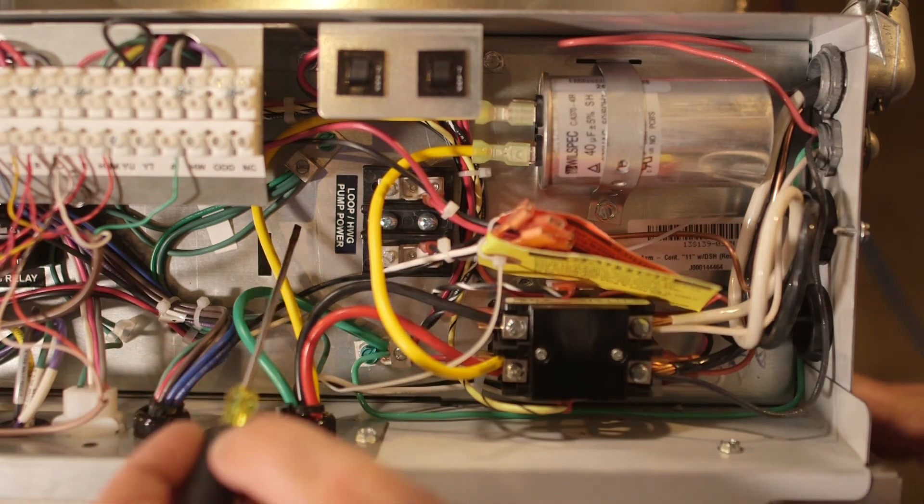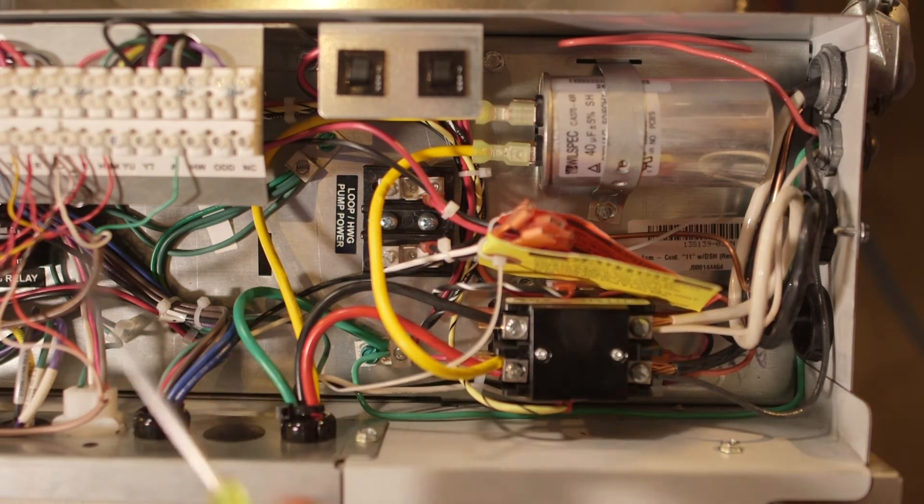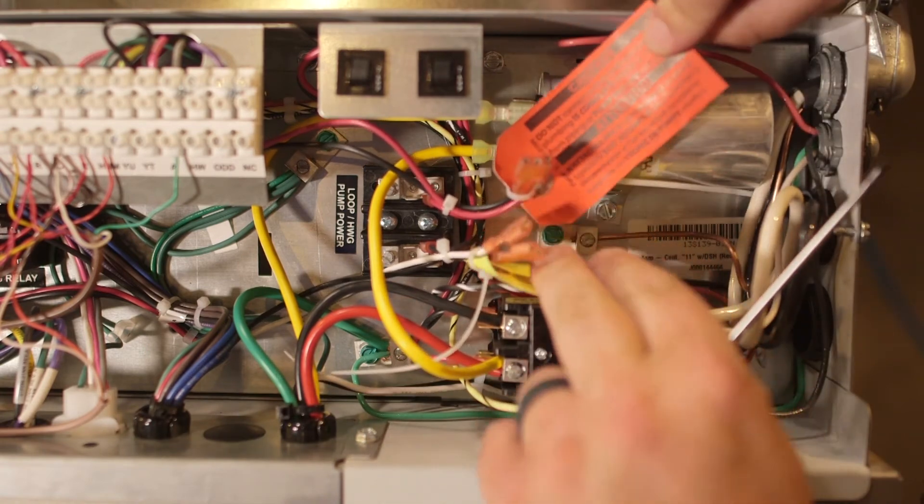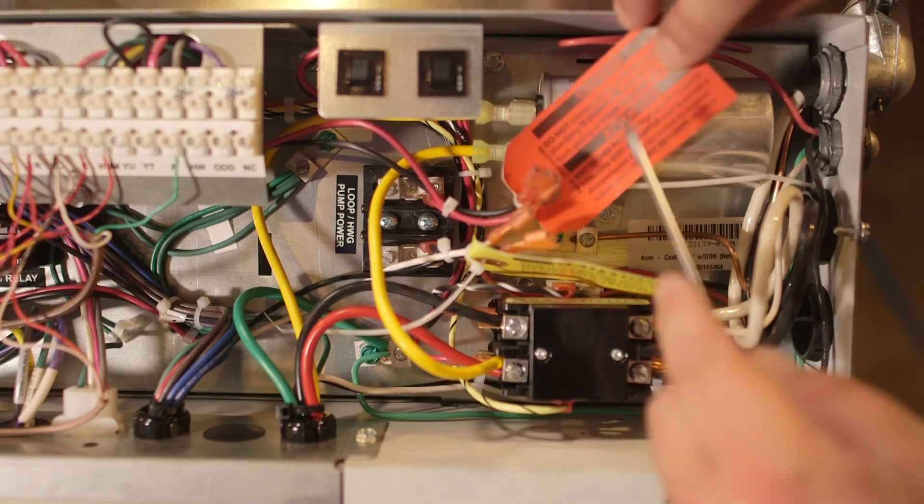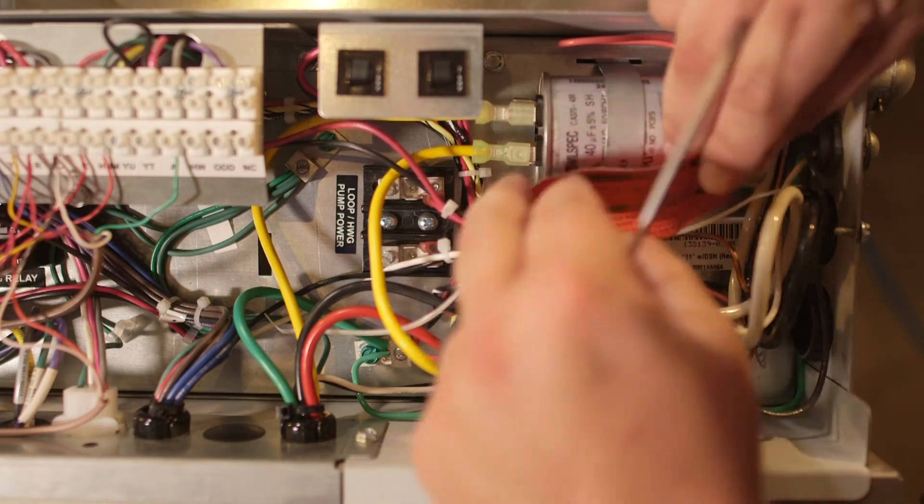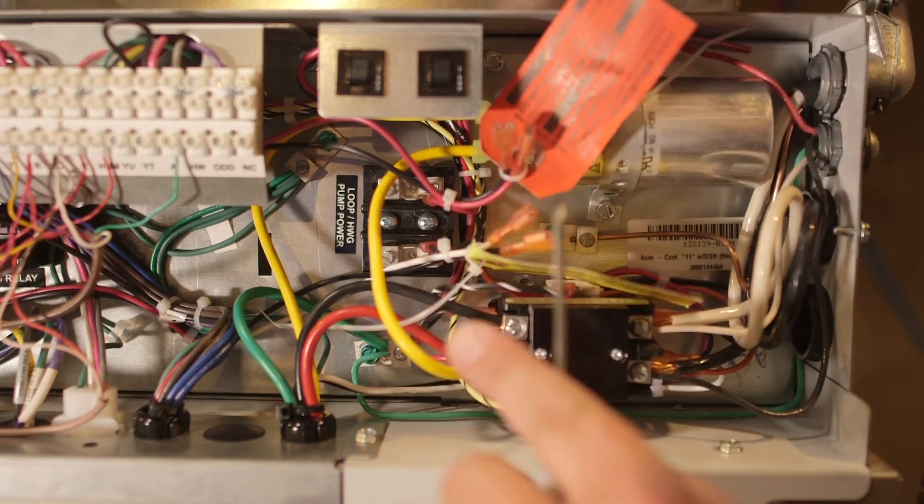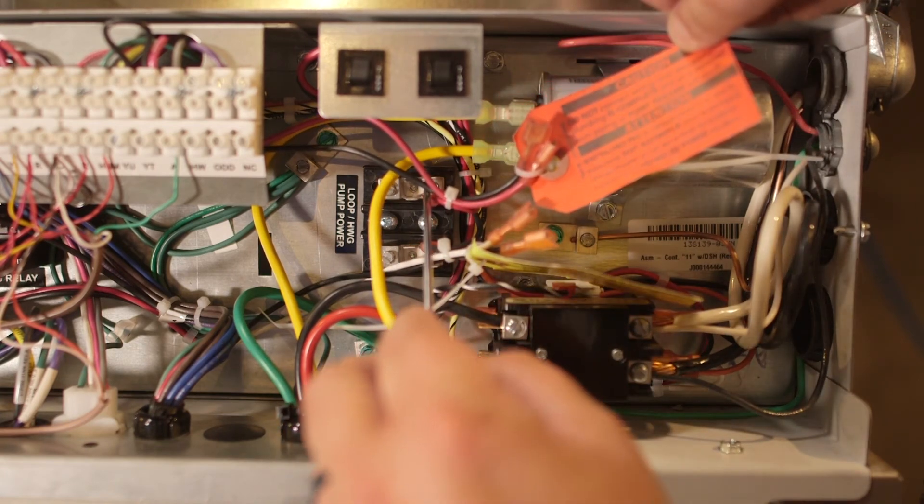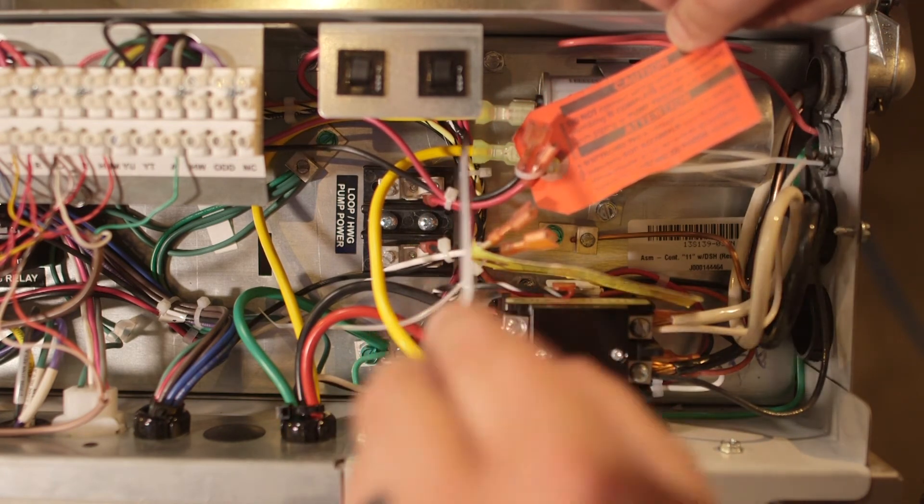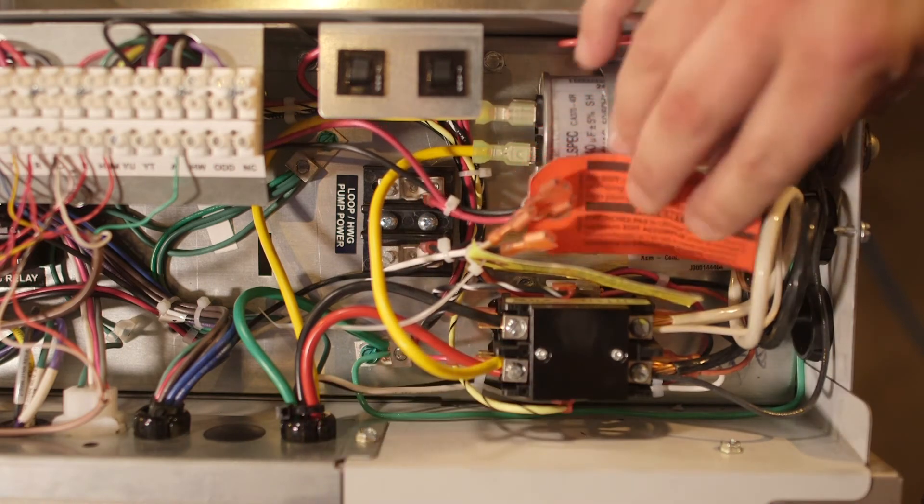This is also where you would hook up your desuperheater pump, which on the YT unit happens to be with the red tag. And it talks about do not hook this up until you have all your piping complete and it's full of water. But it has the two female spade connectors, and you would hook those right onto the male spade connectors on that pump relay.